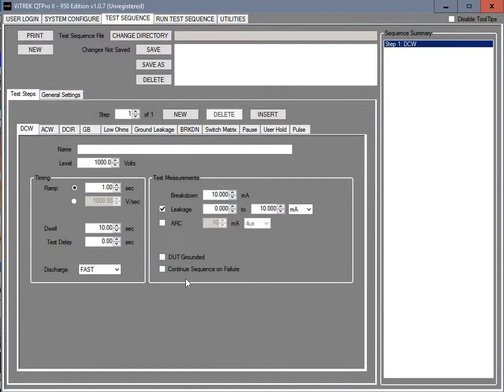The DUT grounded, device under test grounded, that would be only on units that have the high side sense option. And then continue the sequence on fail would mean if you have multiple steps that it's going to go ahead and go to the next steps even on failures. And then it will let you know that at the end of the test.